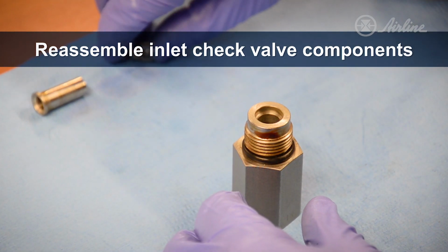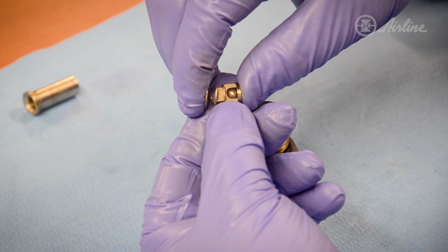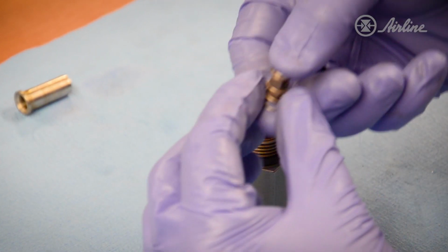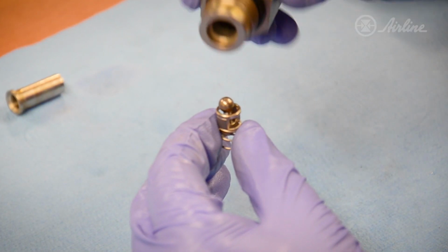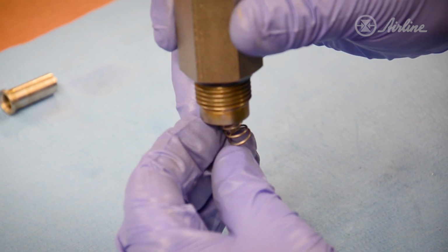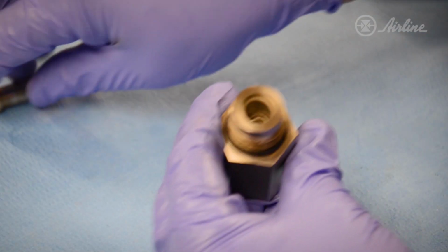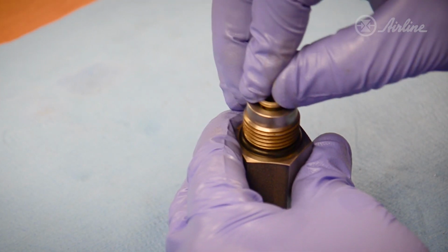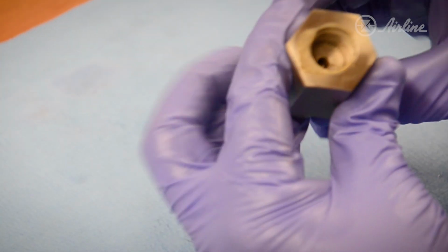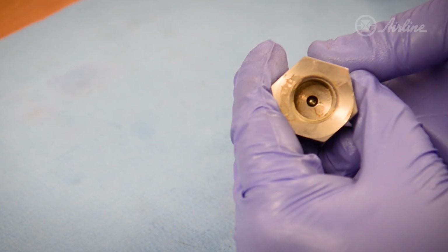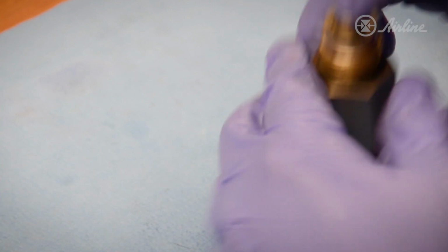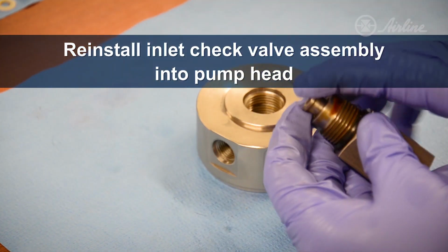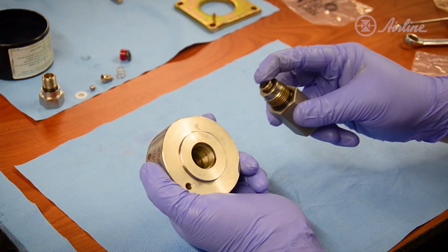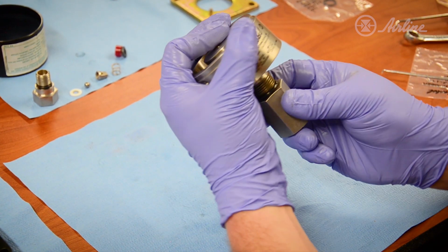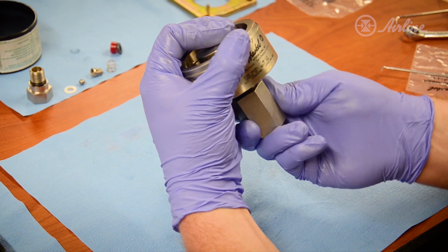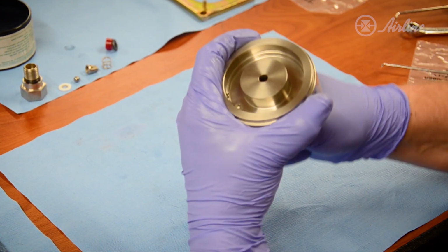Now we need to reassemble the check valve ball, the ball spring, the keeper, ring, and additional spring into the check valve. We hold these upside down and set the check valve assembly over top. When these are in the check valve assembly, we add the standoff tube and check that everything moves freely. We can also see that the check valve ball is seated at the bottom of the inlet fitting. Now we'll reinstall our inlet check valve assembly into the pump head. So carefully hold all of the components in the check valve we just put together and reinstall the inlet check valve into the pump head. This can be tightened down hand tight for now.